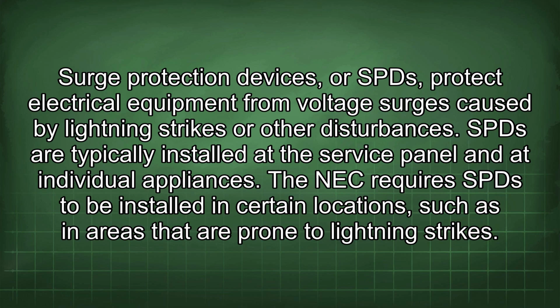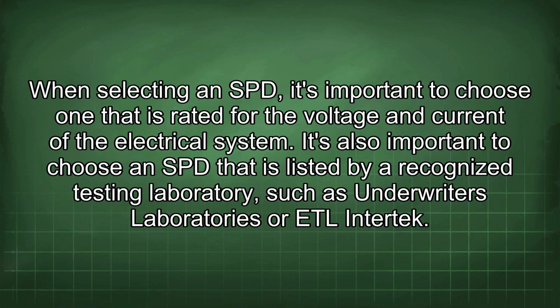SPDs are typically installed at the service panel and at individual appliances. The NEC requires SPDs to be installed in certain locations, such as in areas that are prone to lightning strikes. When selecting an SPD, it's important to choose one that is rated for the voltage and current of the electrical system. It's also important to choose an SPD that is listed by a recognized testing laboratory, such as Underwriters Laboratories or ETL Intertek.